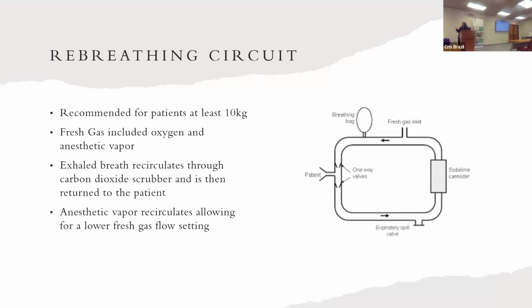But I'll kind of explain the rebreathing circuit. So when a patient is at least 10 kgs, they qualify to be put on the rebreathing circuit. And basically the fresh gas equals oxygen and anesthetic vapor. It's combined and it goes out together. When the patient exhales, it recirculates through the circuit and it gets scrubbed in a CO2 scrubber. And then the gas is actually returned to the patient. So it's continually flowing through and recirculating. So in that sense, you don't have to have the flow as high because it's being recirculated in the system.